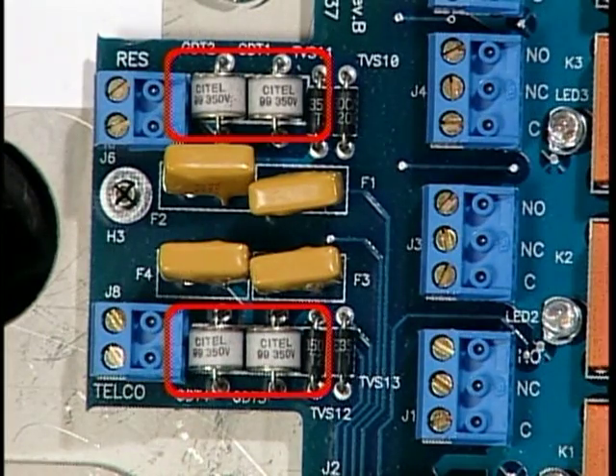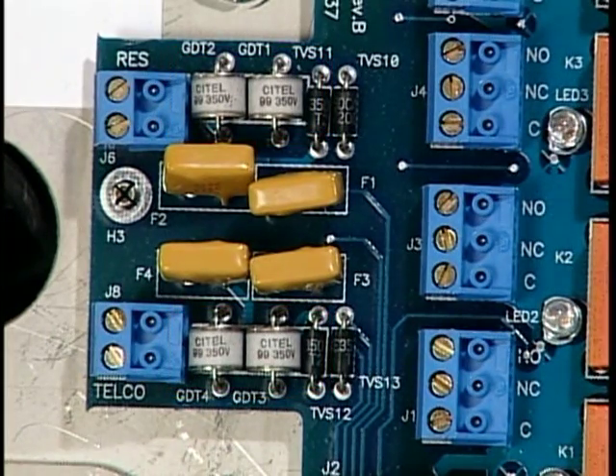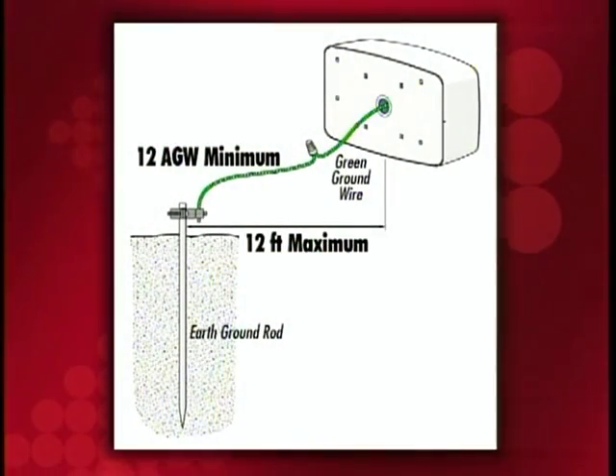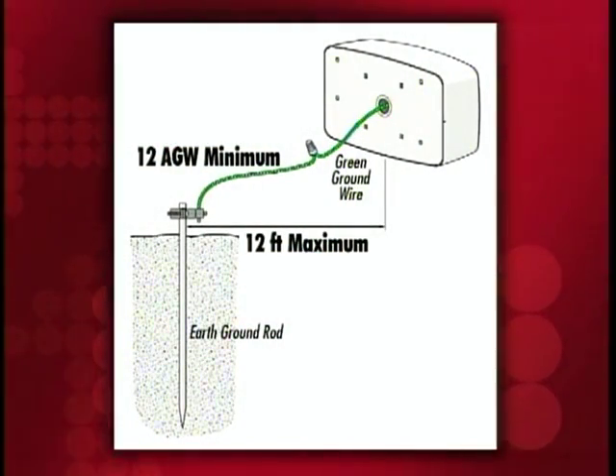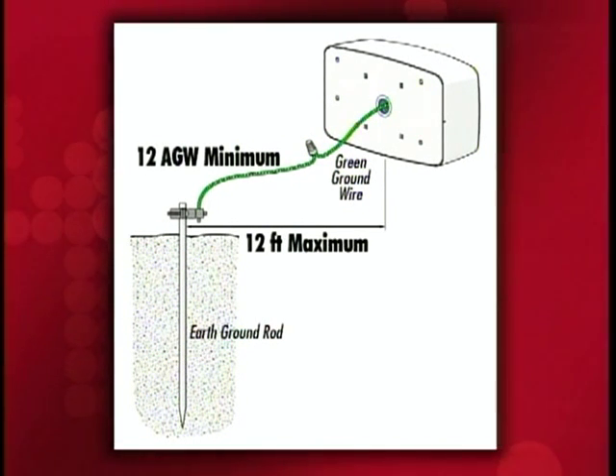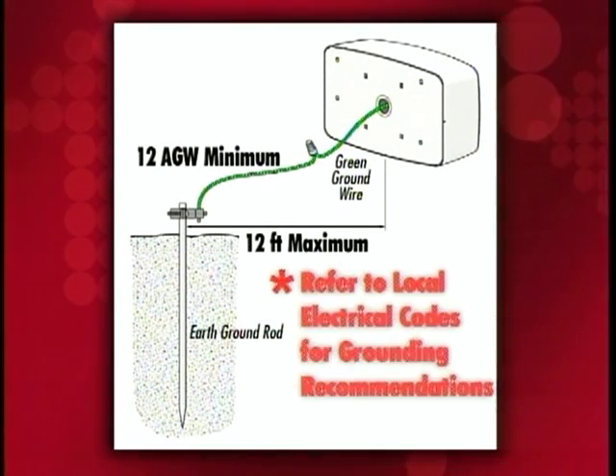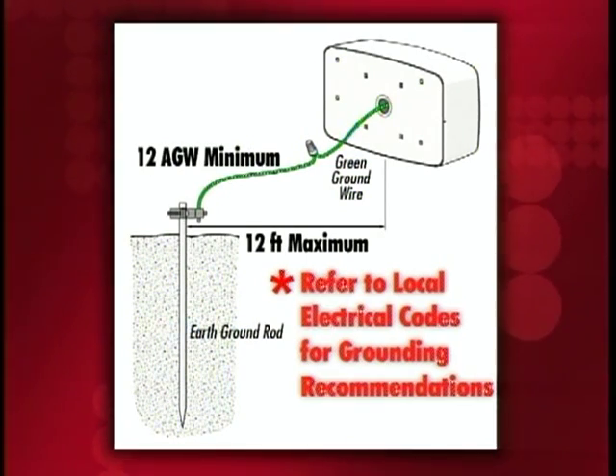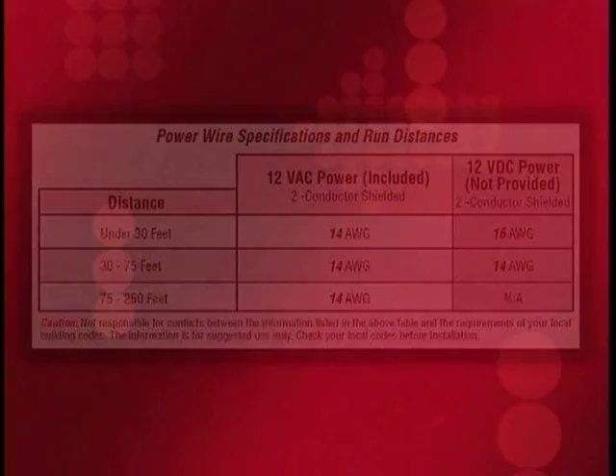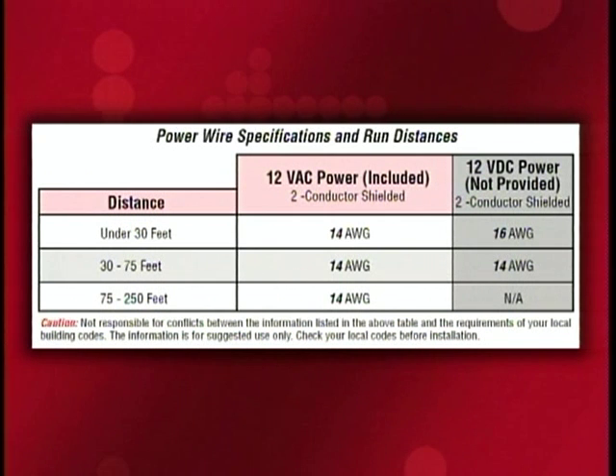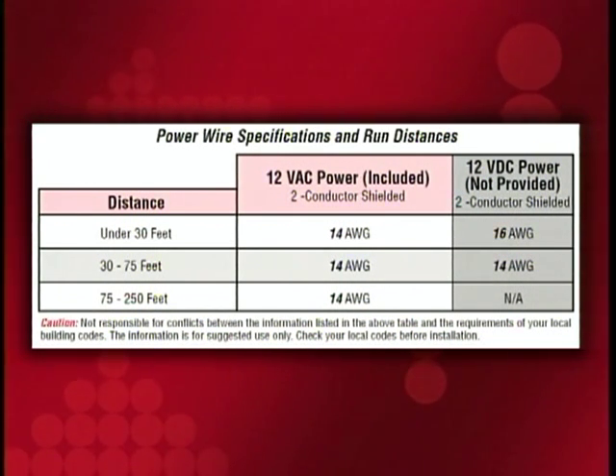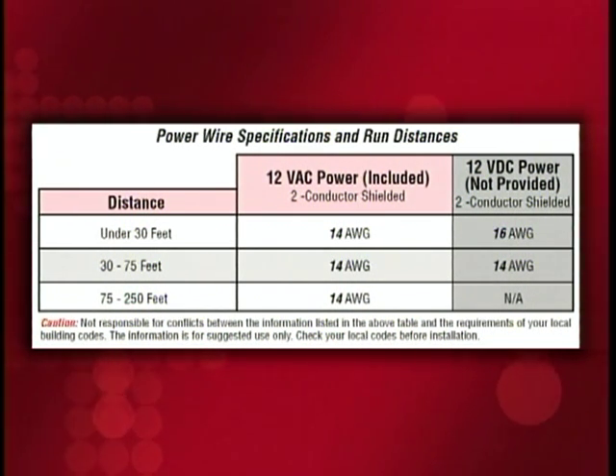However, in order for the surge suppression to be effective, the unit must be properly grounded. An earth ground must be located within a maximum of 12 feet of the unit and should be wired with a minimum of 12-gauge wire. Refer to local electrical codes for grounding recommendations. When wiring input and output devices, it is important to use the proper gauge of wire to ensure proper operation of the devices. Refer to the wiring gauge chart included in the installation manual.